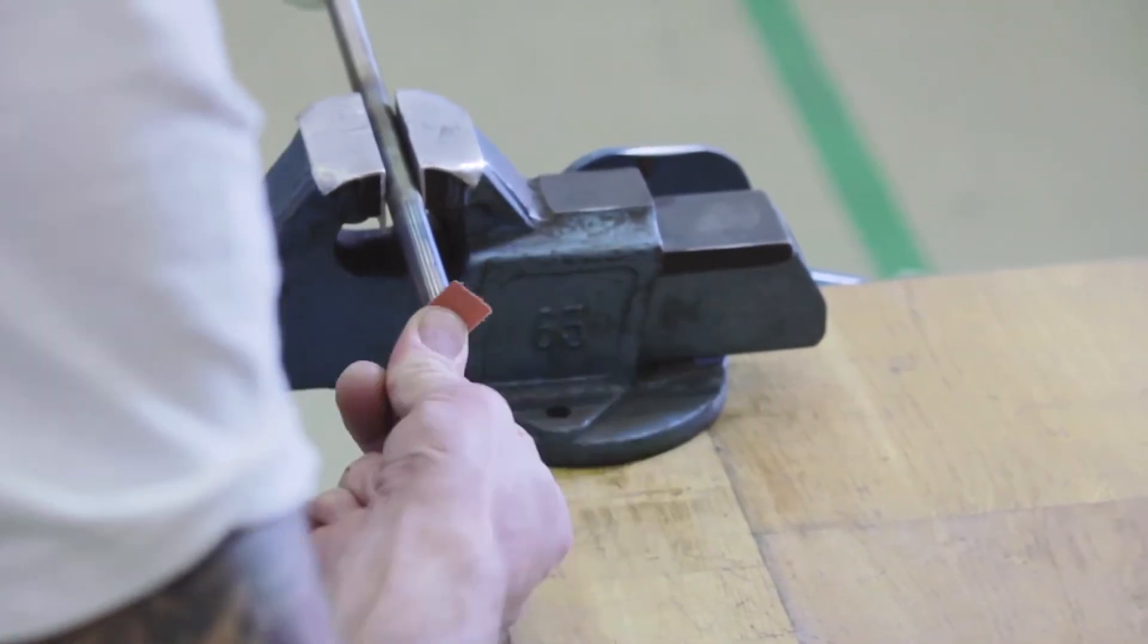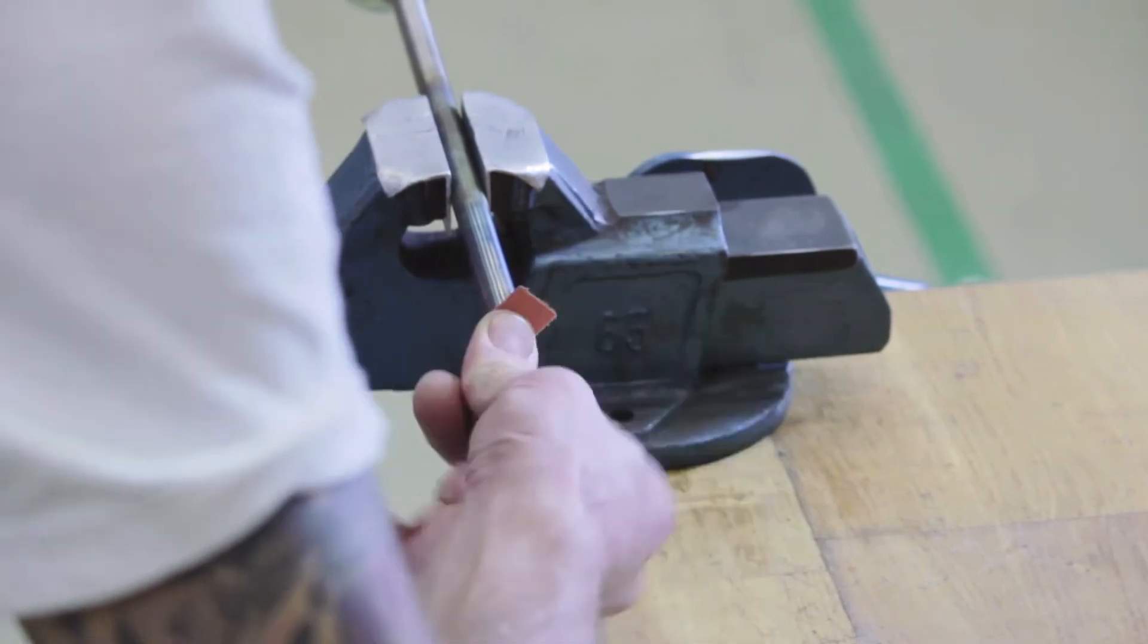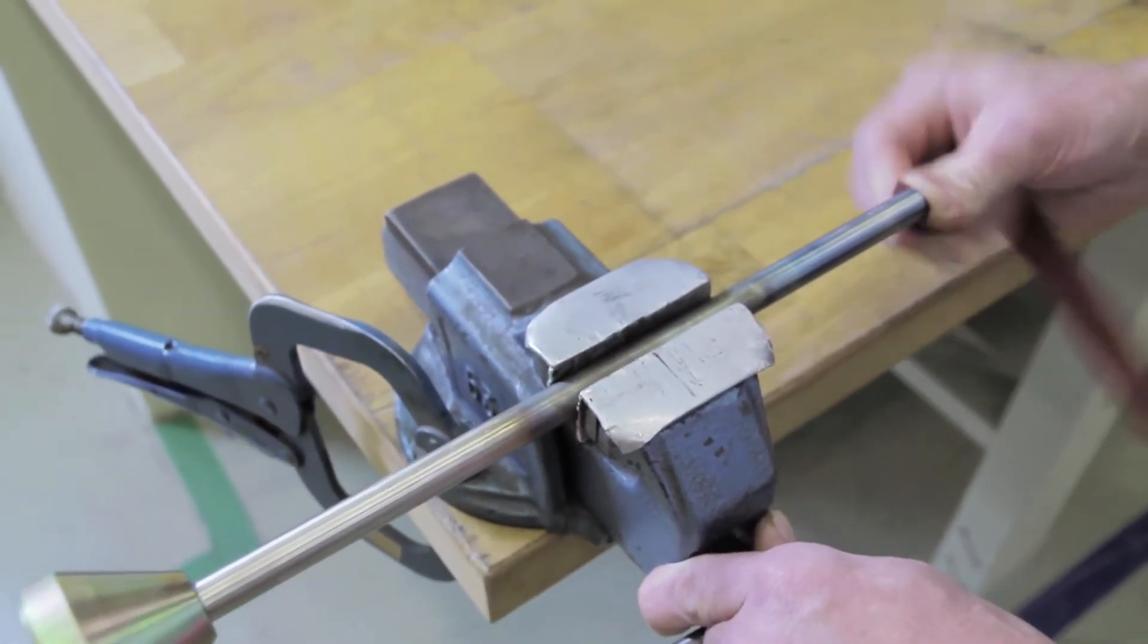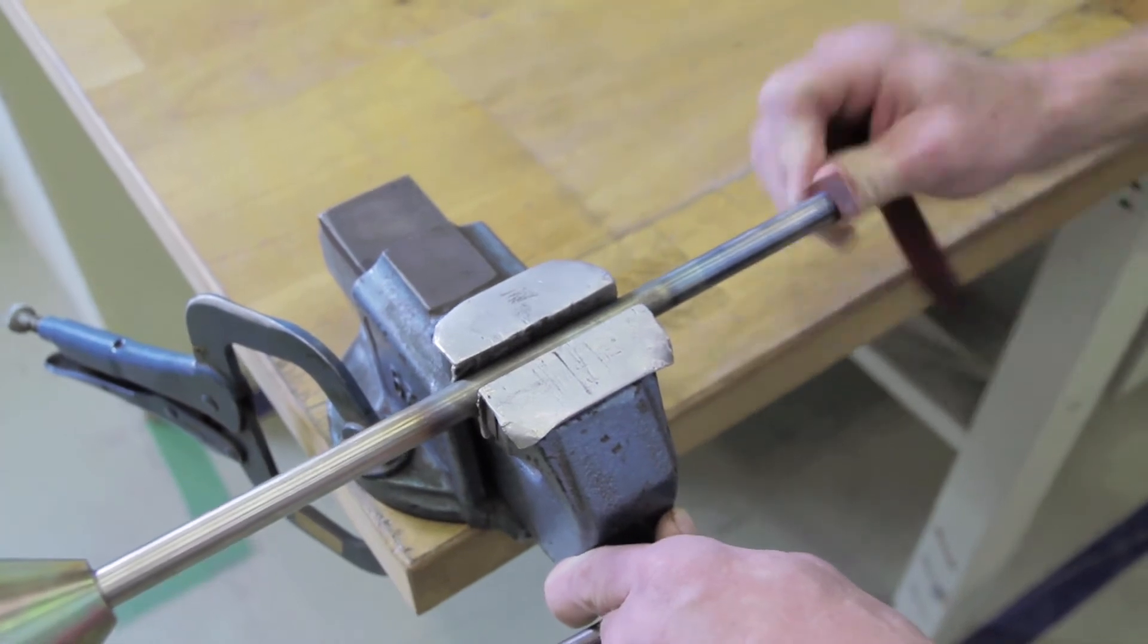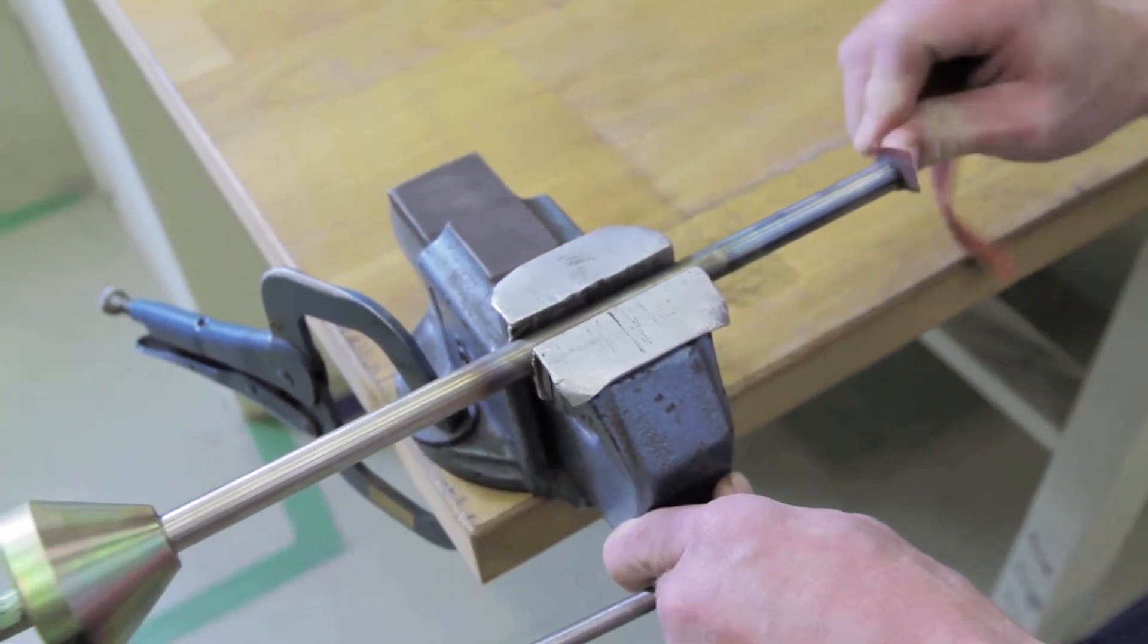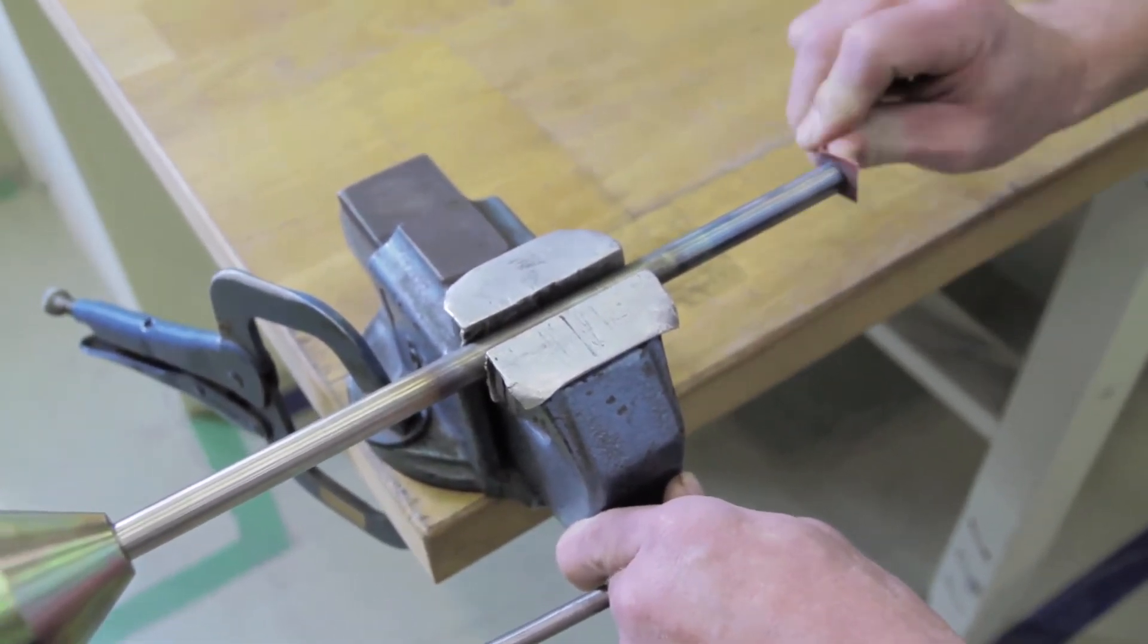Emery paper with grit size 320 is sufficient to remove the oxide but still fine enough not to reduce the probe diameter too fast. Be gentle to the edge and try to just grind the sectional surface.